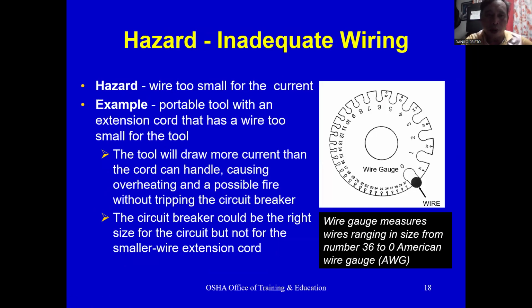Hazard: inadequate wiring. Wire too small for the current. Example: a portable tool with an extension cord that has a wire too small for the tool. The tool will draw more current than the cord can handle, causing overheating and a possible fire without tripping the circuit breaker. The circuit breaker could be the right size for the circuit, but not for the smaller wire in the extension cord. We have here a wire gauge example so that you can measure the actual size of a wire.